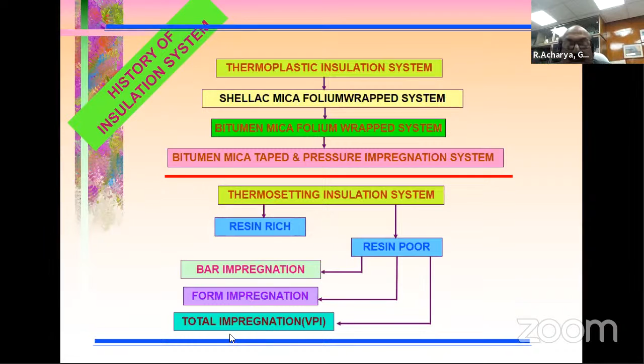It has a direct bearing to ensure the healthy operation of the winding in flexible operation when the machine runs with a very varied load. So this plays a very important role that we will discuss in the backdrop of the total impregnation VPI insulation system.